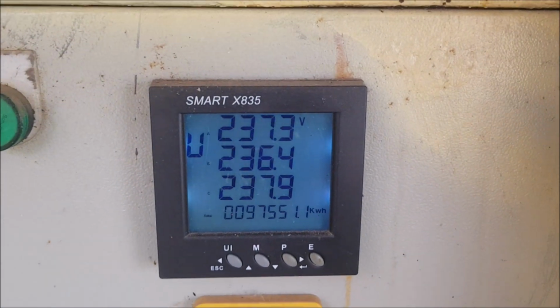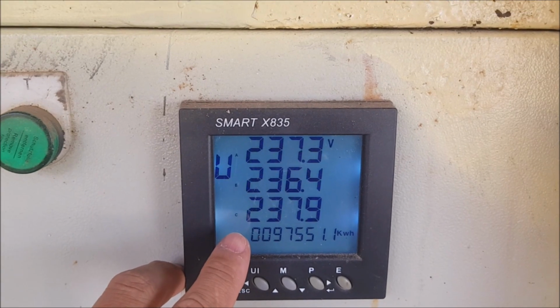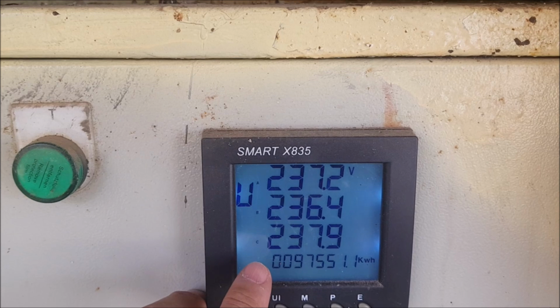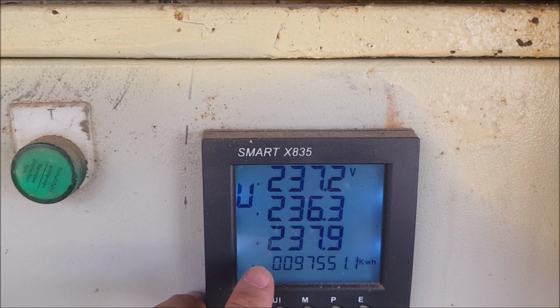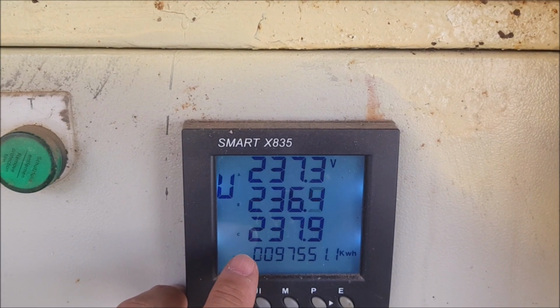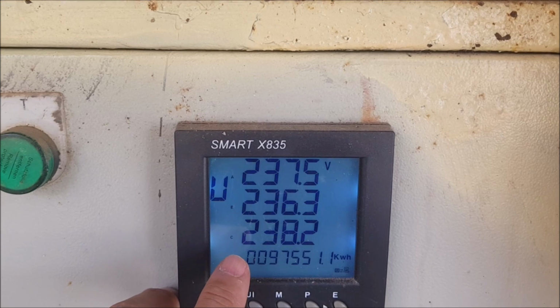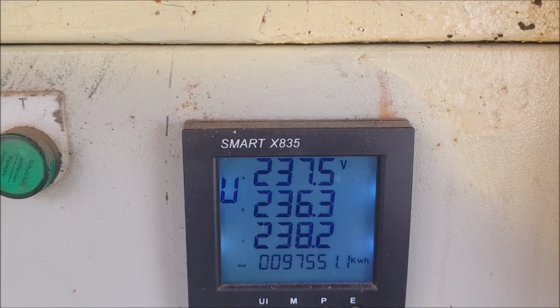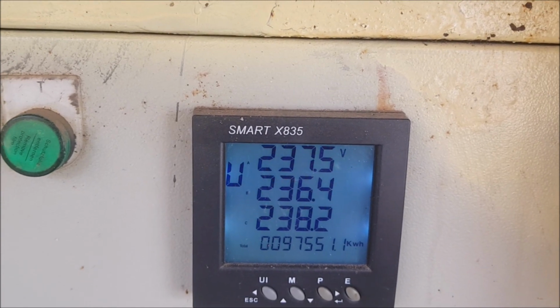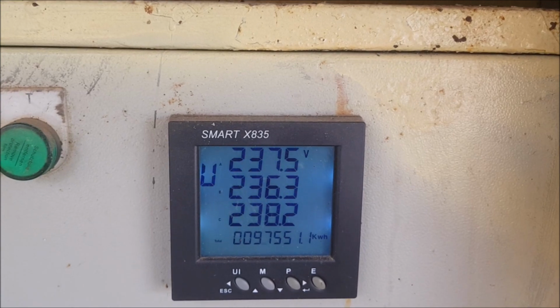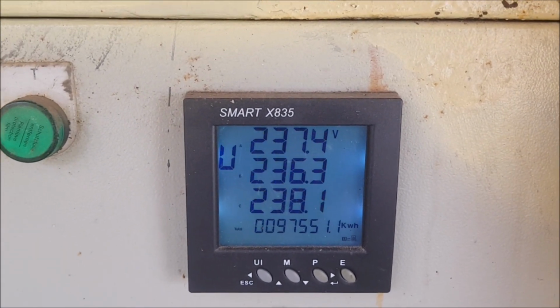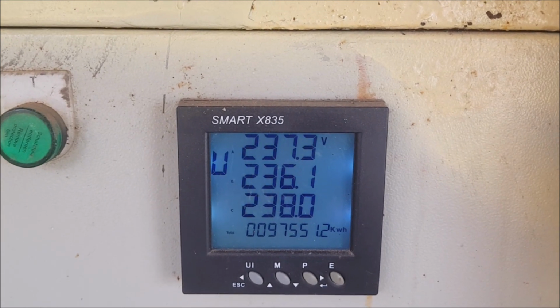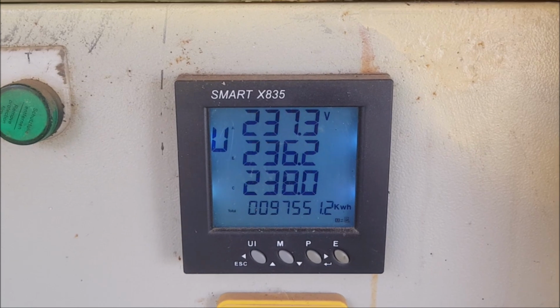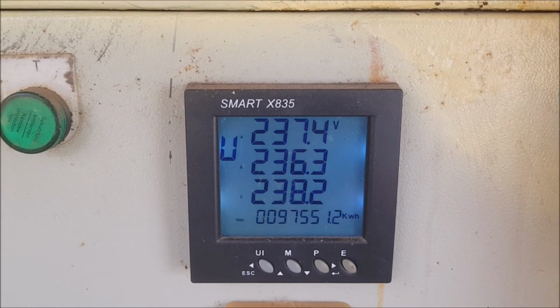Okay, we are at the MDB. Let's take a look at the meter here. We just looked at phase 3 in the garage, which was over 241 volts, the limit allowed here in Thailand. Here, right at the transformer, this phase is showing 238. So we have about 4 volts less at the grid entry point, so it's absolutely no problem with voltages. Everything is legal and fine, if you can tell why this phenomenon happens.